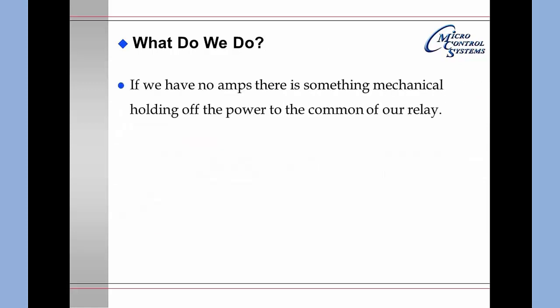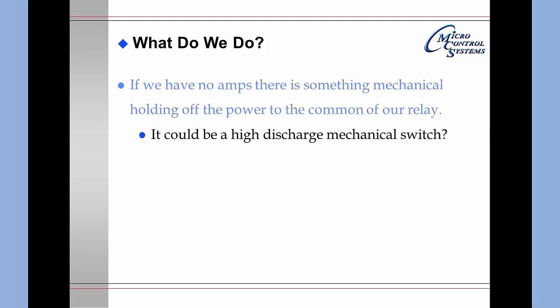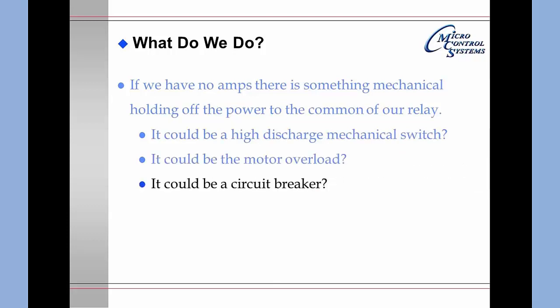So what do we do? If we have no amps, there is something mechanical holding off the power to the common of our relay. It could be a high discharge mechanical switch, the motor overload, or a circuit breaker. You need to go back and pull the wiring diagram to find out what items of a mechanical nature are in front of our relay where the control power is going through before it gets to our relay.